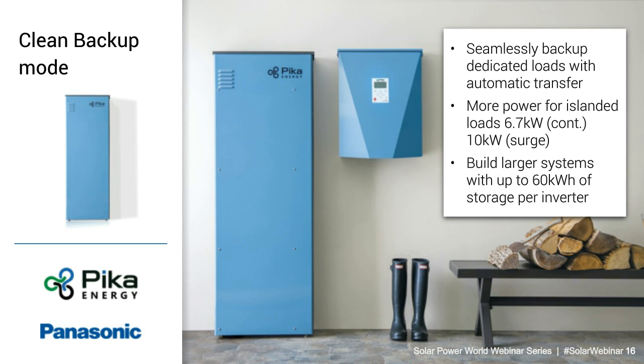More detail on clean backup mode. The automatic transfer switch in the inverter will automatically shunt power to the dedicated loads when you're in backup mode. When the grid is lost, it just clicks over instantaneously to power those loads. Again, you get that higher power for the islanded load, so 6.7 kilowatts continuous, 10 kilowatt surge from your battery. And you can build as big of a bank as you want, up to 60 kilowatt hours for each inverter that's installed on site.